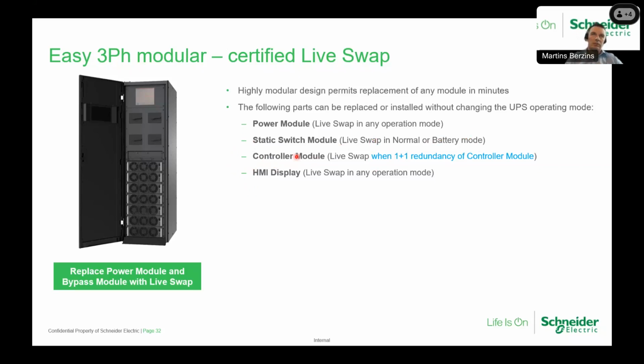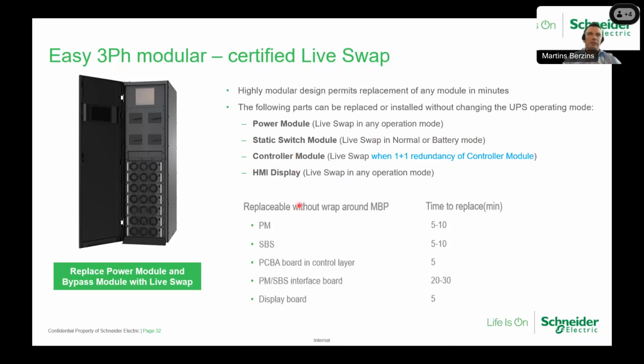So if you look from the time perspective, how much time does it take? For the power module, it will take 5 to 10 minutes to replace such components. The static bypass switch also can be replaced in 5 minutes, the control layer in 5 minutes, and the display board also in 5 minutes. So basically, most of the sensitive and critical parts of the UPS can be replaced without putting the UPS in external bypass mode, and this is a very important feature which Schneider is implementing in all our modular UPS models.